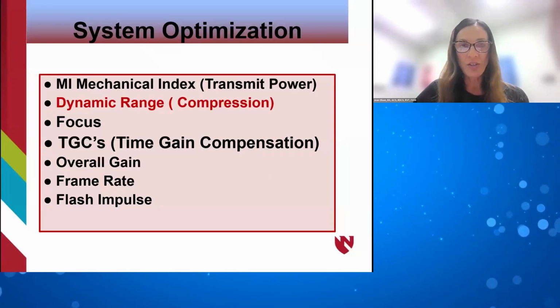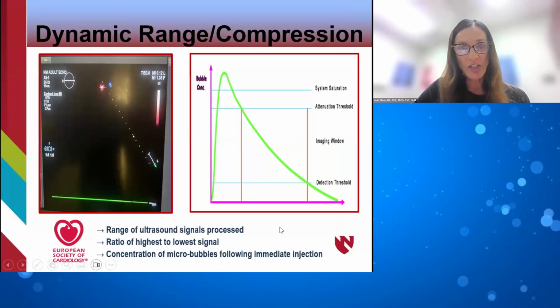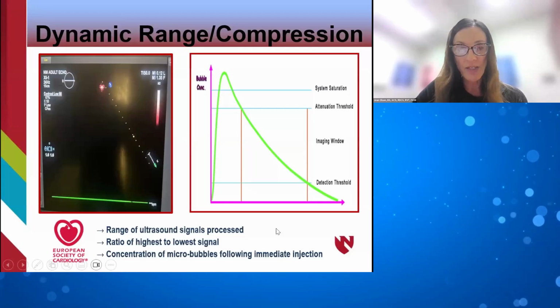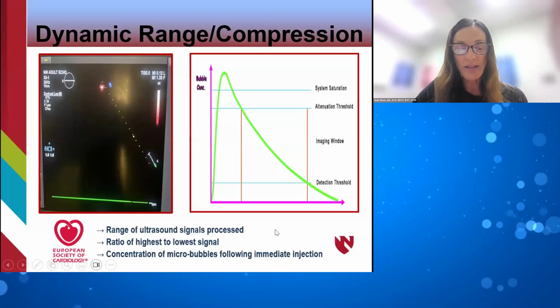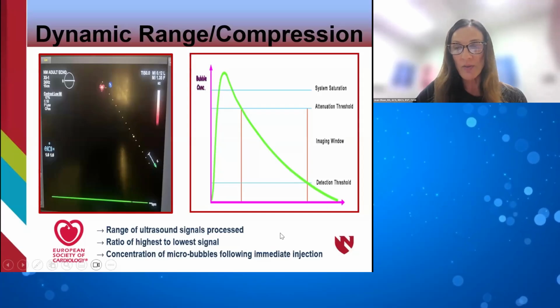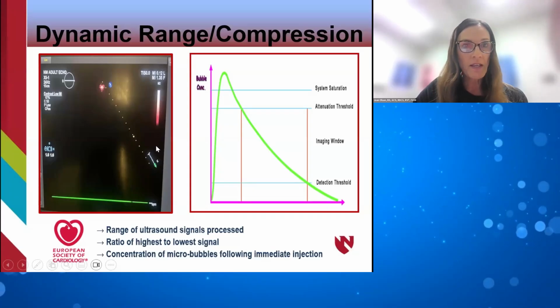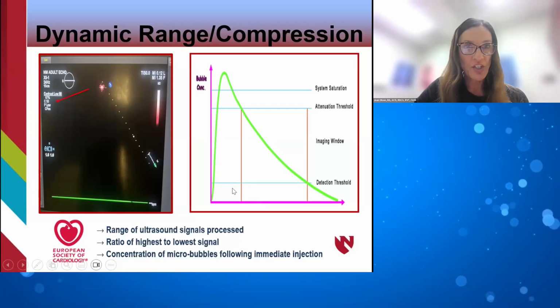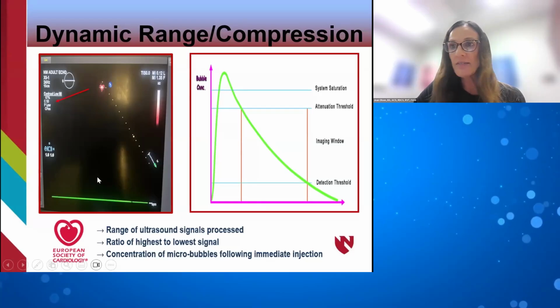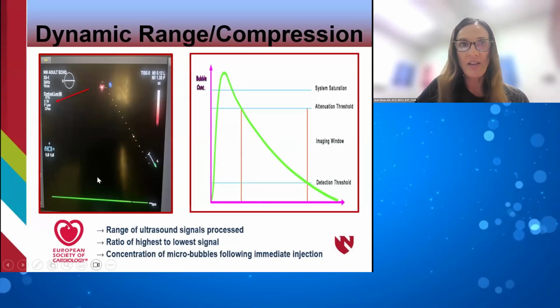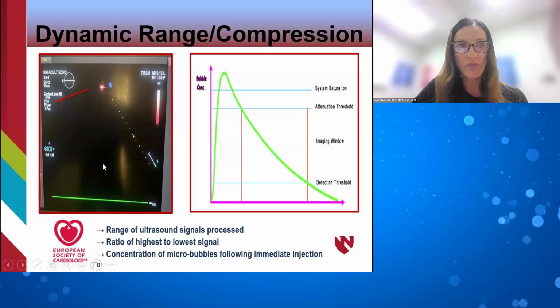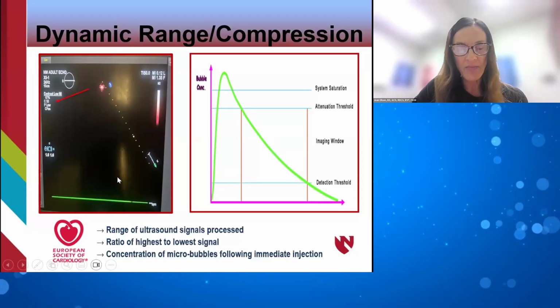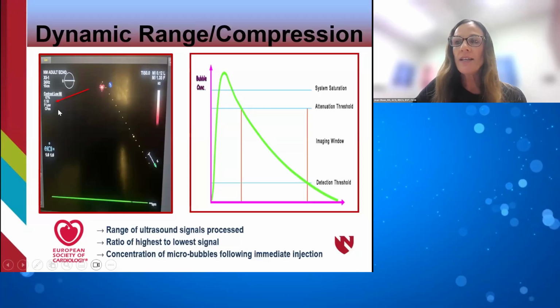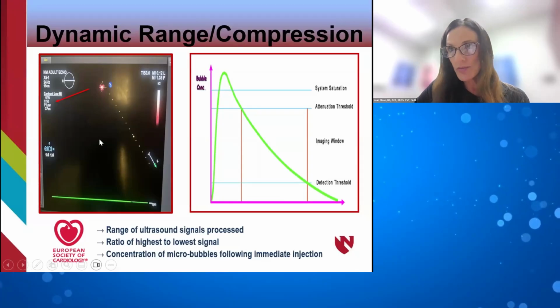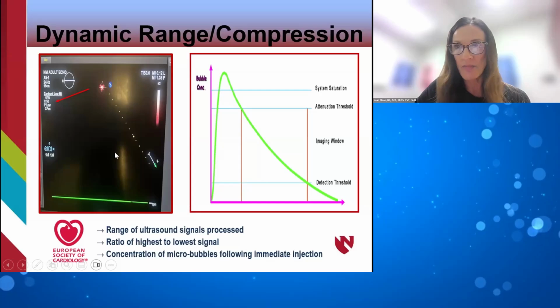Your dynamic range, your compression, is the range of ultrasound signals processed. It's the ratio of the highest to lowest signal, and it's the concentration of microbubbles following the immediate injection. Usually we set it around 50, but that could depend on your machine. Like I said, this is our machine, and ours is usually set around 50. And persistence, which I don't have in my slides here, is usually either turned off or set low when you're doing the low MI imaging.